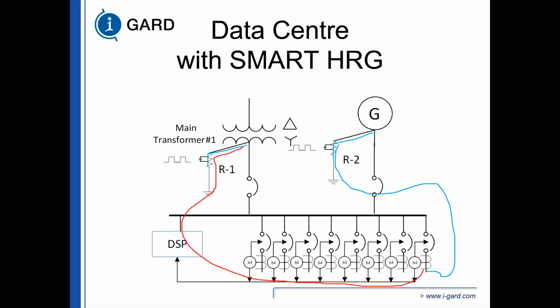So we have one HRG system, and the operator of that facility looks at one location and one location only to determine whether they have a ground fault on their system or not, because it's independent of whether they're running on the generator or on the transformer. The fault doesn't care where it's coming from, it just cares where it's going to, but it's coming from the origin of the fault, which is right here. And now when you turn on the pulsing, it's telling you to look in feeder number 1, 2, 3, 4, 5, 6, 8. Feeder number 8 has the ground fault.